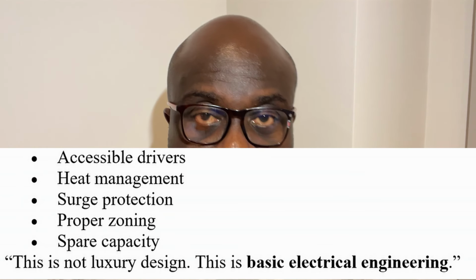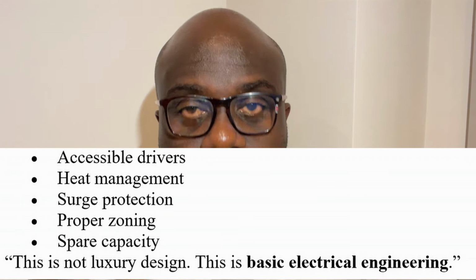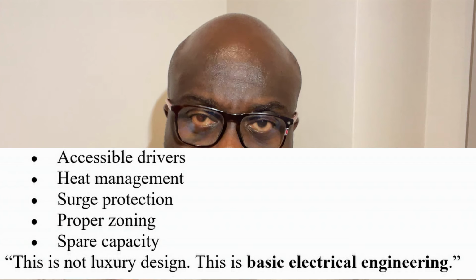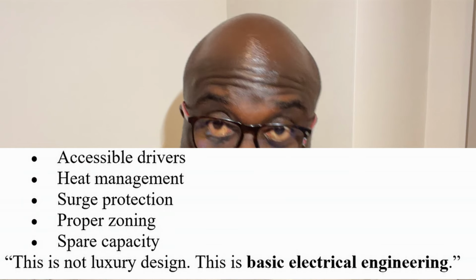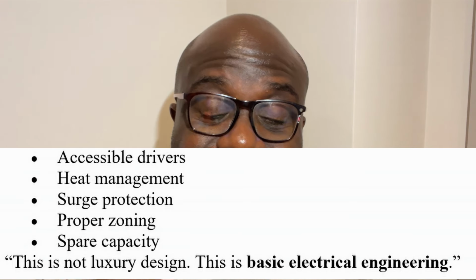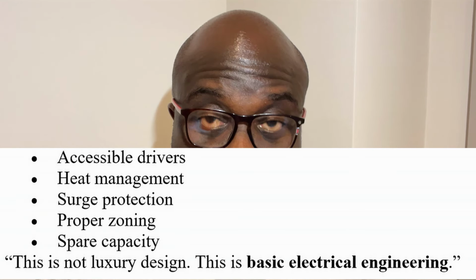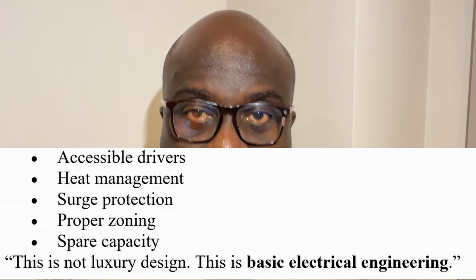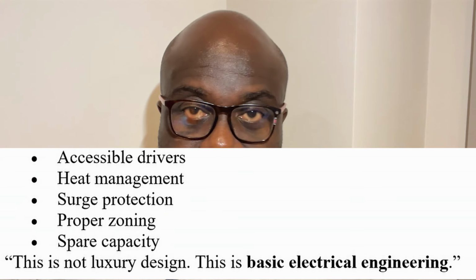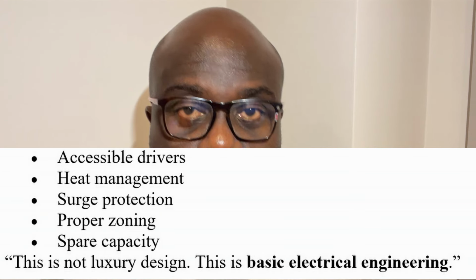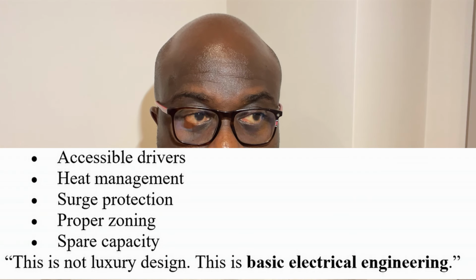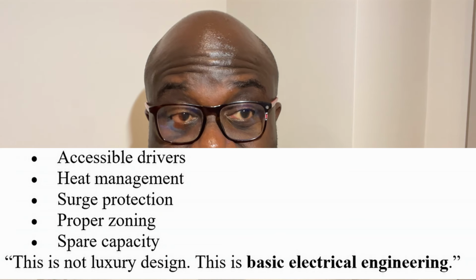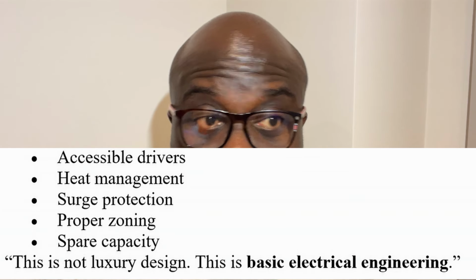So tell your electrician, look, I'm not going to purchase the distribution board until you've put all the wires through the pipes and you know exactly how many circuits you're connecting the breakers to. That way the electrician can buy the correct size distribution board, whether it's an 8-way TPN or a 12-way TPN. This is not luxury design. This is basic electrical engineering.